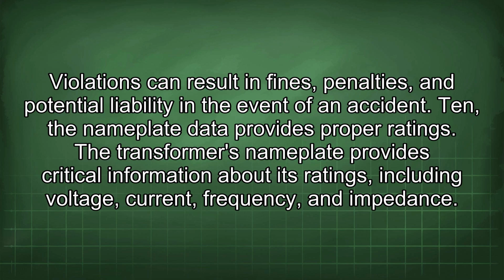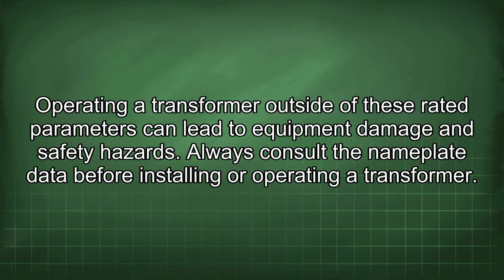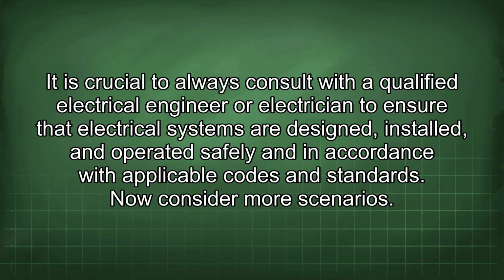10. The nameplate data provides proper ratings. The transformer's nameplate provides critical information about its ratings, including voltage, current, frequency, and impedance. Operating a transformer outside of these rated parameters can lead to equipment damage and safety hazards. Always consult the nameplate data before installing or operating a transformer. It is crucial to always consult with a qualified electrical engineer or electrician to ensure that electrical systems are designed, installed, and operated safely and in accordance with applicable codes and standards.